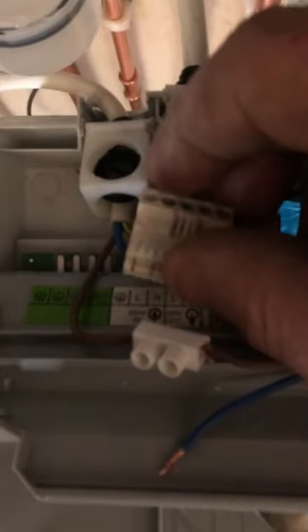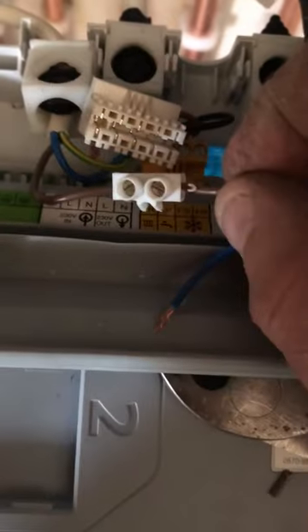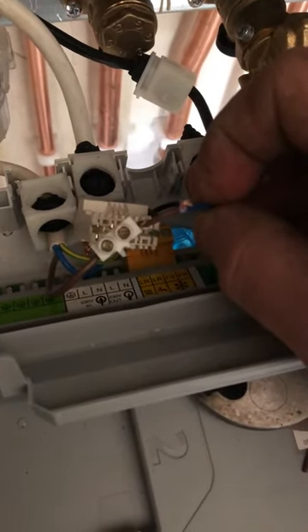Here we are inside the Worcester boiler. Obviously make sure you've got the power turned off — which we do. We are taking the live wire from the fuse spur out of this connection here, which goes into the boiler, and putting it into a connector block with one of these wires from the condensate pump. These two wires from the condensate pump are just a float switch — a high level float switch which acts as a cut-out.